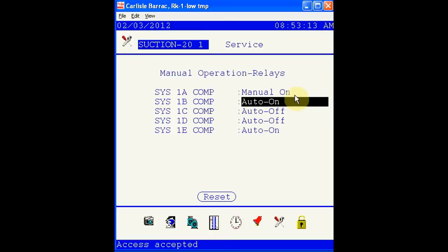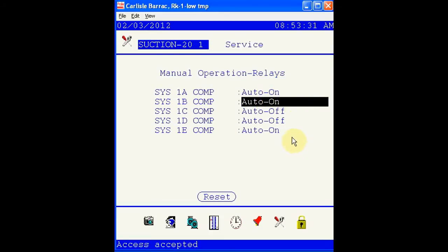This override will stay in place until removed by the user. There are two ways to remove the override. It's possible to remove it by just selecting the reset button at the bottom, or we can simply go back to the point, switch back to auto, and the override is removed. It's also possible to override or offset sensors using the service screen.